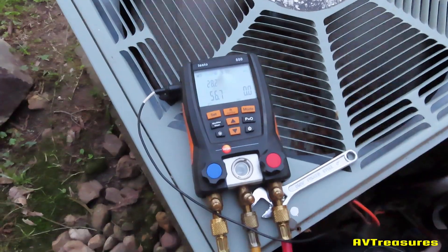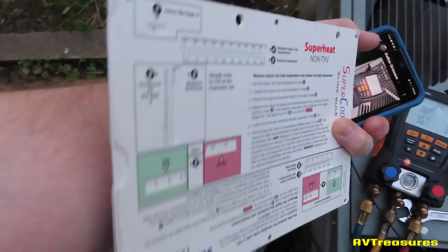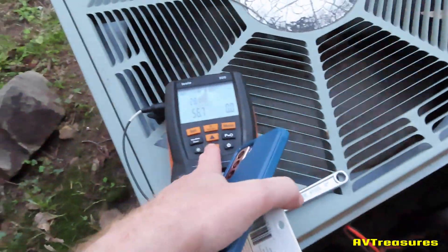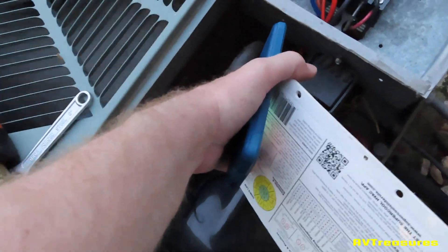We should have about 12 to 15 degrees of superheat. That's a SuperCool slide rule here. So we're definitely low in charge. This line is kind of cool but it's 59.44 degrees — it's going to be a lot colder than that.